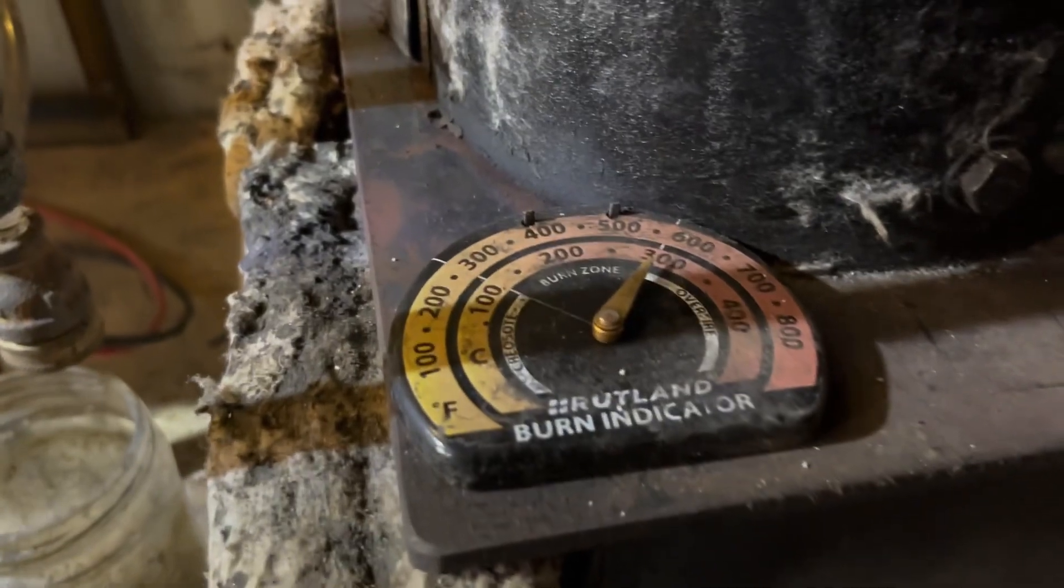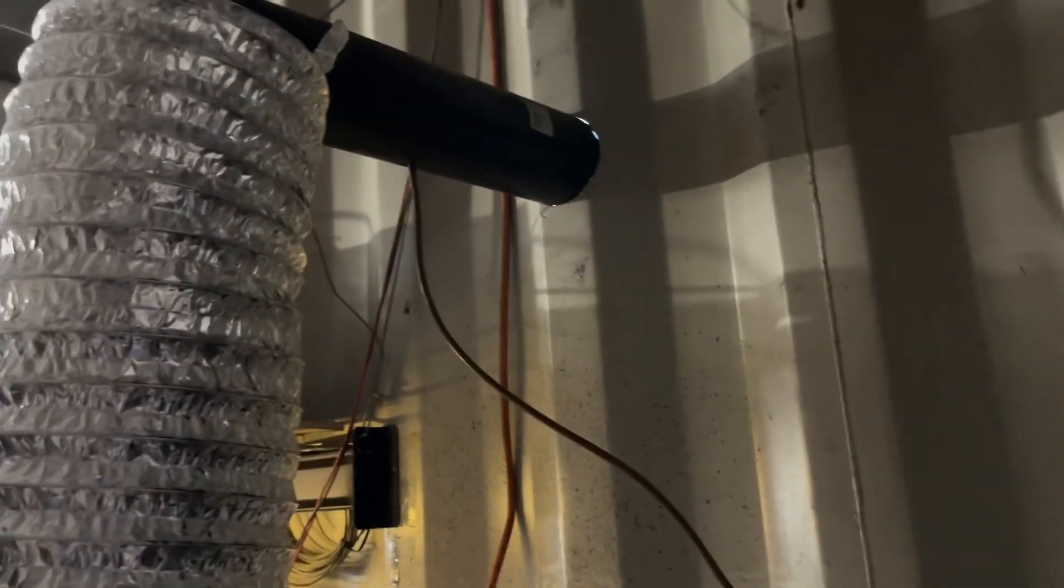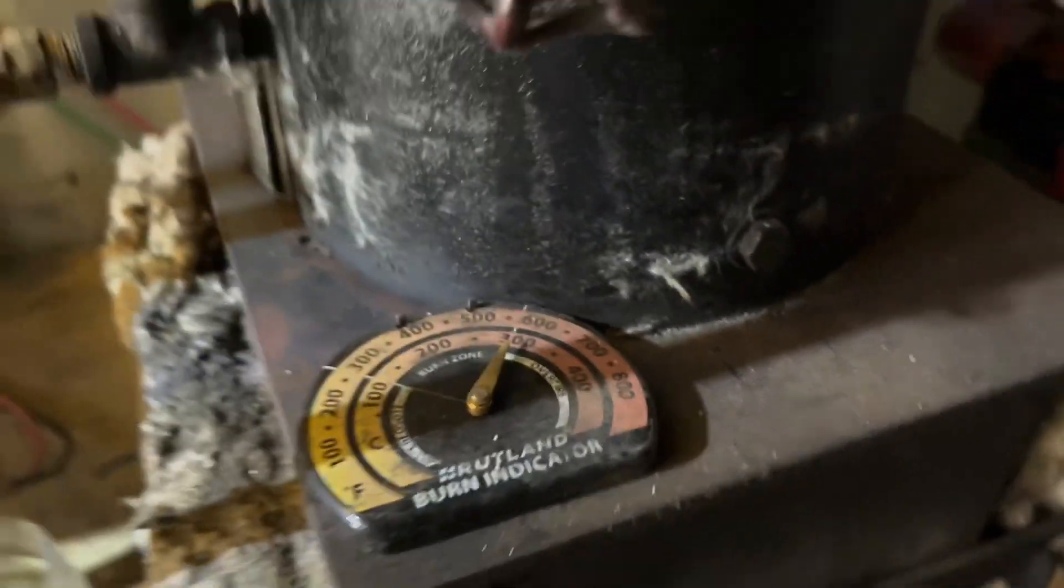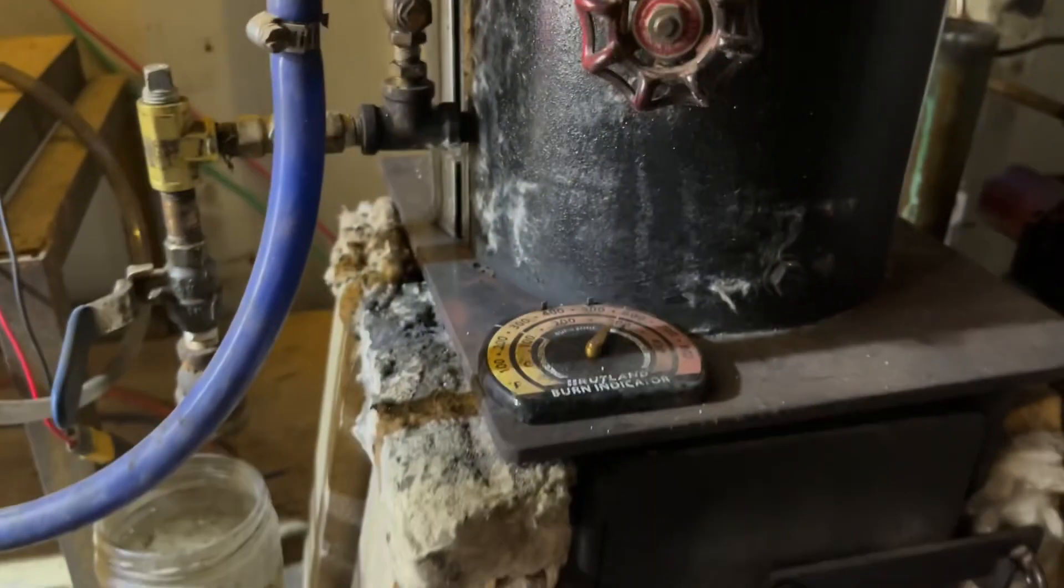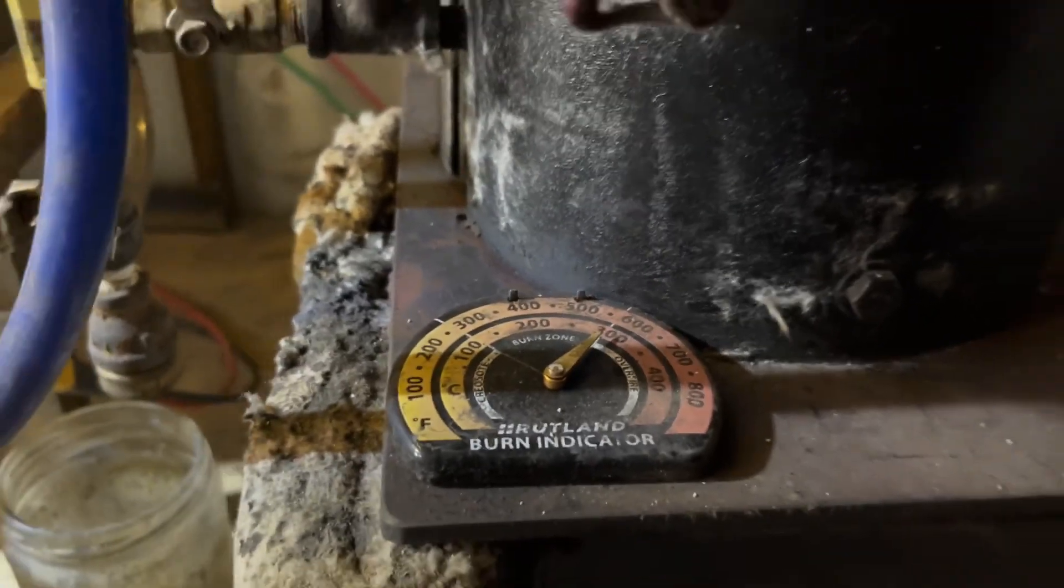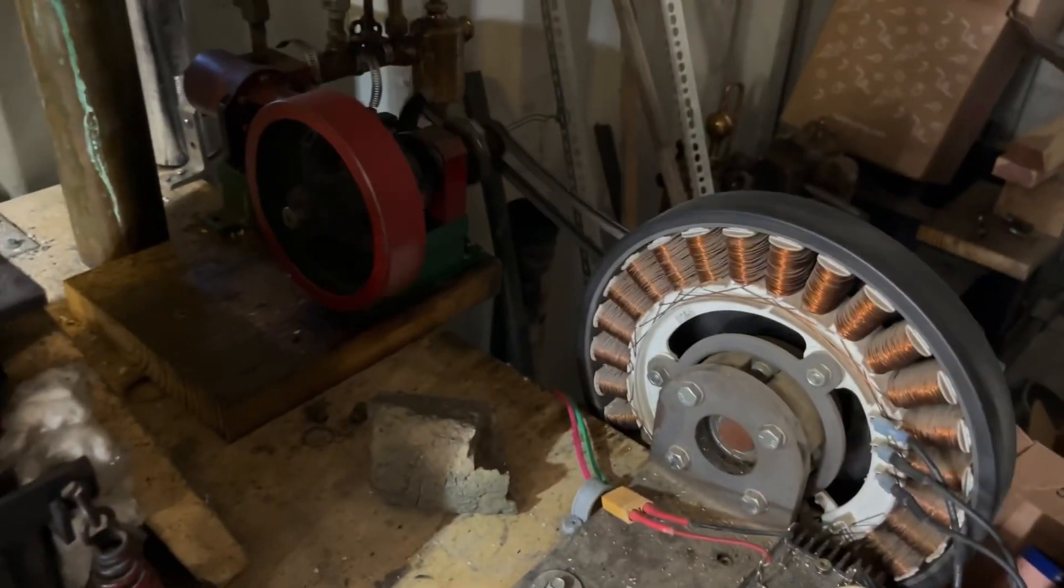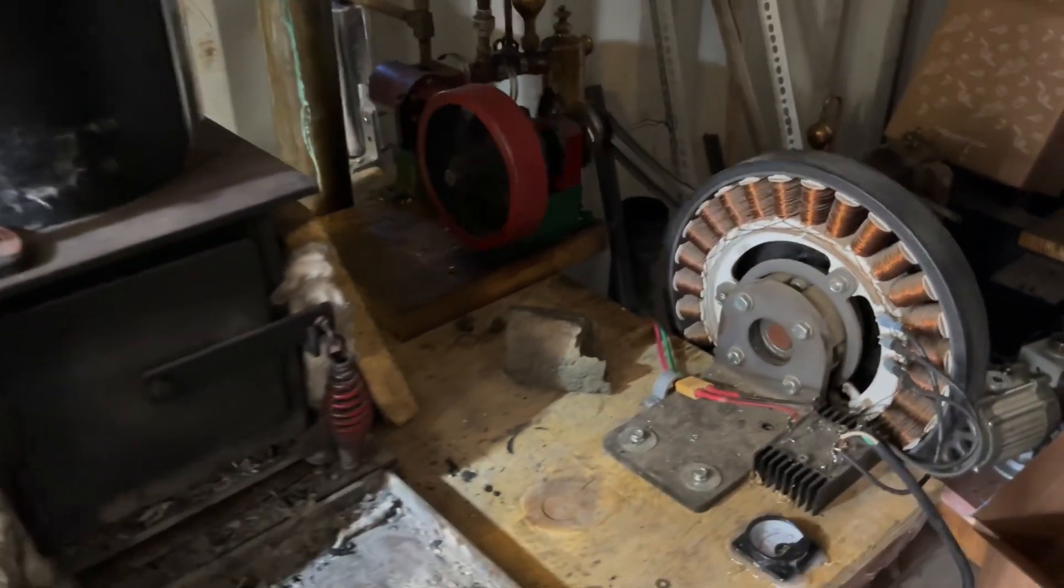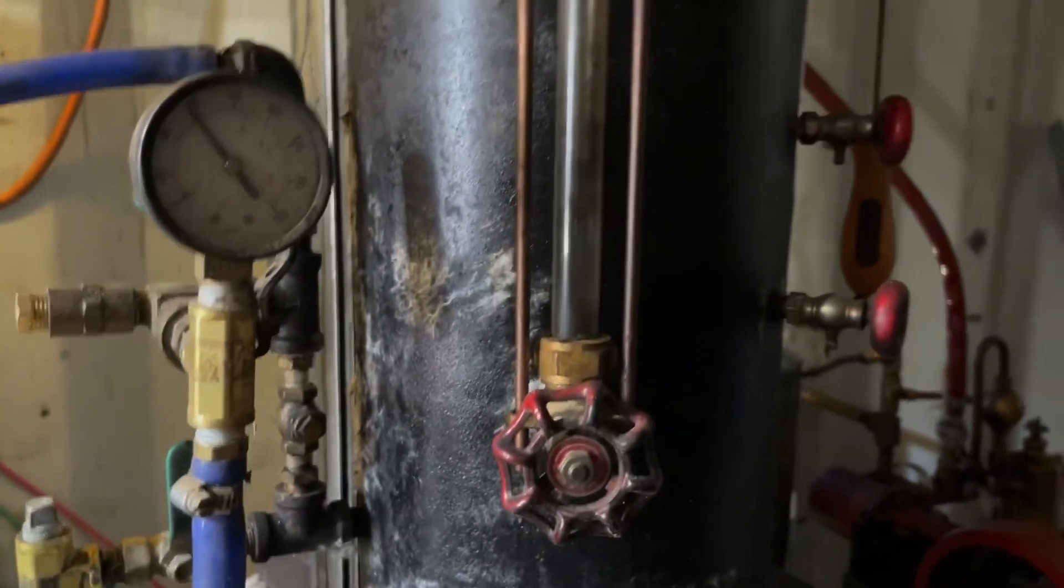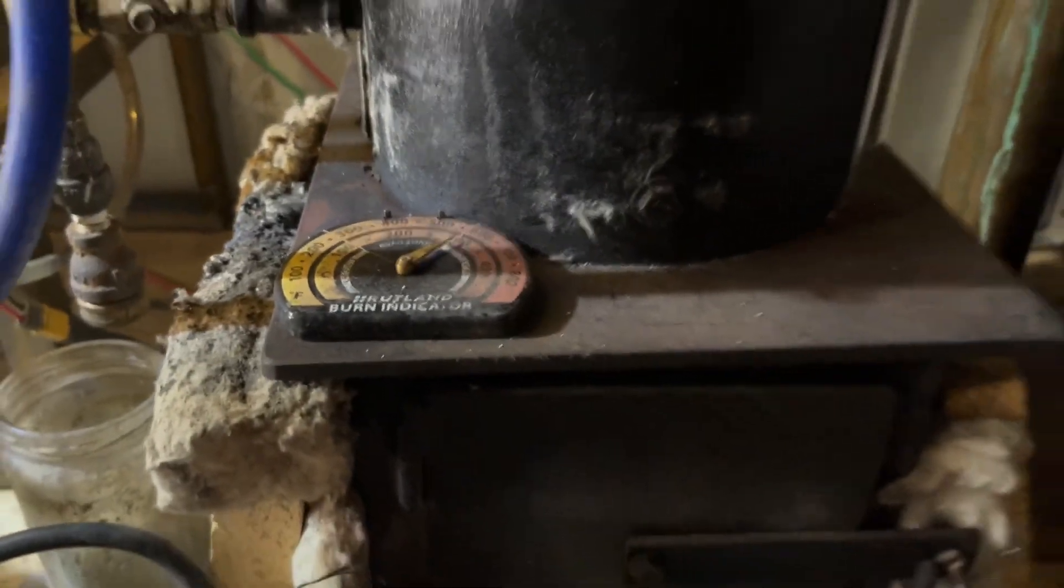Getting, that's a really hot fire. Normally, I don't run it this hot, but this is my first time I'm really testing that little draft guy there. So, this thing should actually perform pretty well right now. That's, you know, you're going to be an overfire, but, you know, the temperature drops down and you've got water in the boiler. That is probably still a bit on the hot side. Normally, I like to keep it around 500 tops. And I'll crack the valve open and release some more steam out of this, even though we're only sitting at, like, 18 pounds with about half water in the boiler.